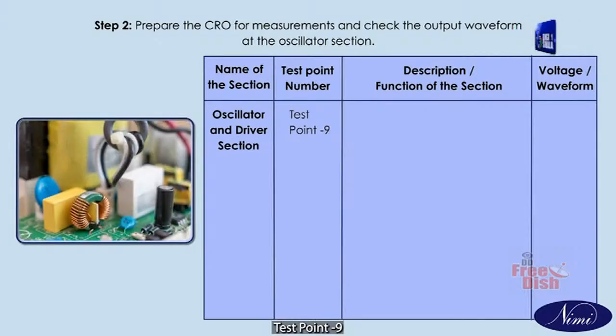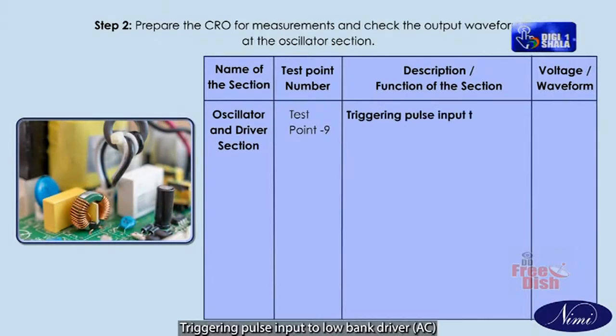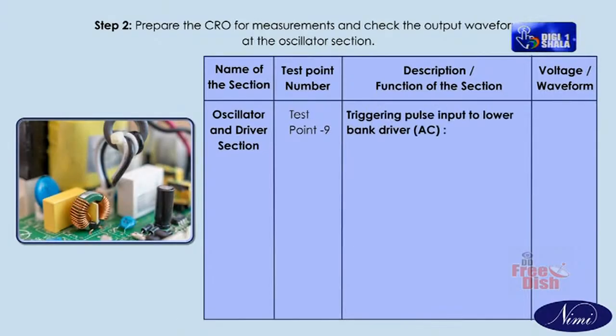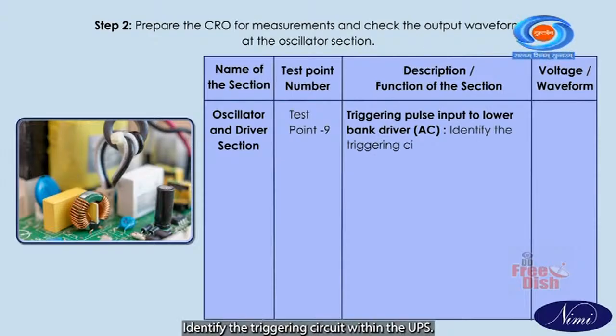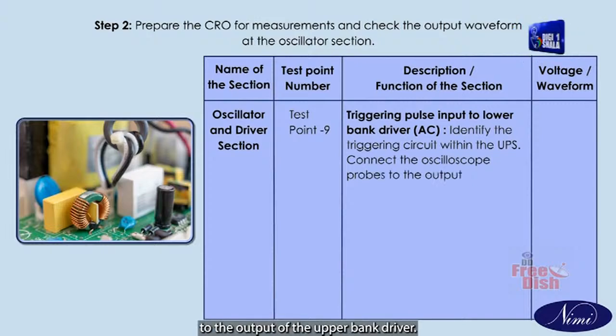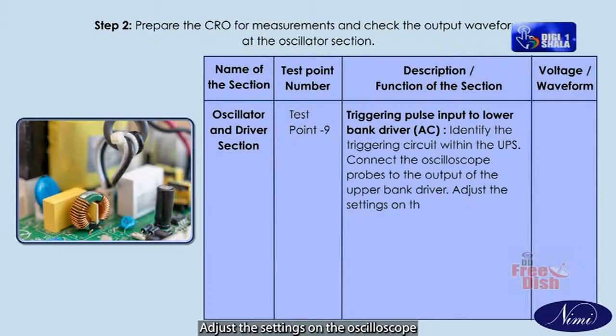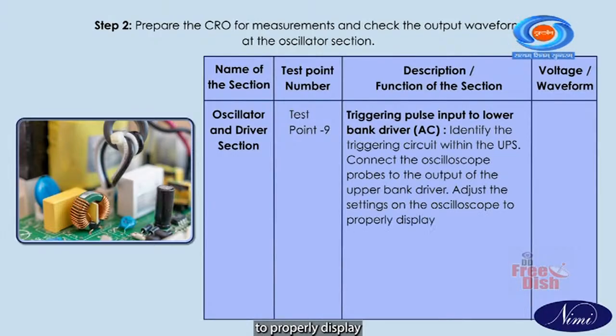Test point 9. Triggering pulse input to lower bank driver AC. Identify the triggering circuit within the UPS. Connect the oscilloscope probes to the output of the upper bank driver. Adjust the settings on the oscilloscope to properly display the triggering pulse waveform.